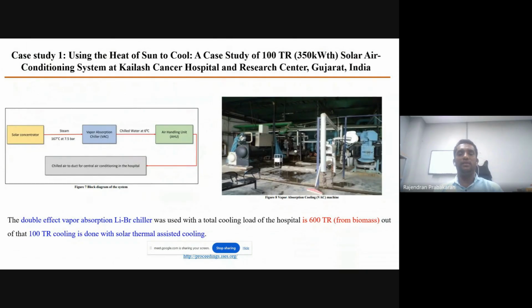there is a case study, where about a 100 TR solar air conditioning system was installed in the Kailash Cancer Hospital and Research Center in Gujarat. They used solar concentrators combined with a vapor absorption based refrigeration system. This vapor absorption system was run by biomass energy. The total capacity of this lithium bromide based VAR system is 600 TR, out of which 100 TR was supported by the solar thermal systems.